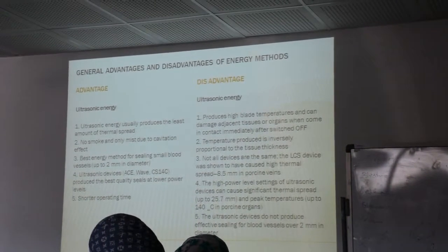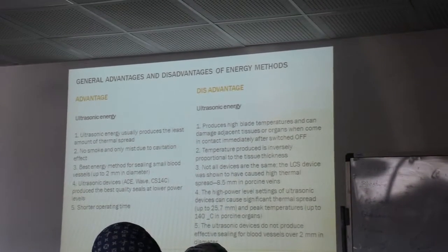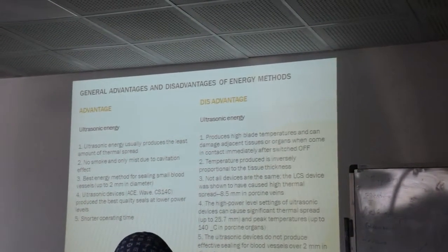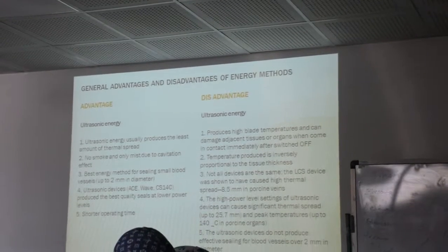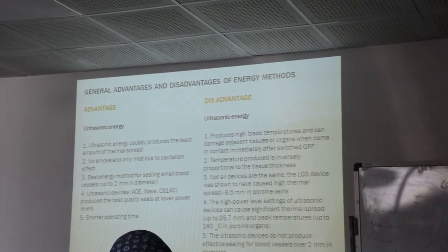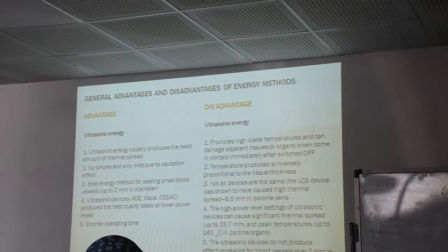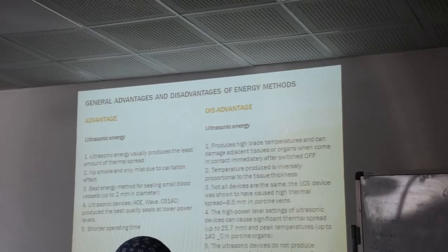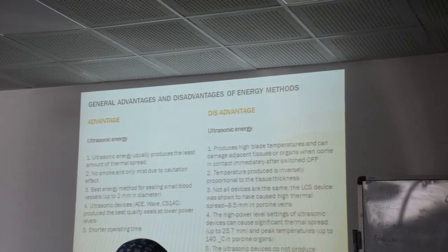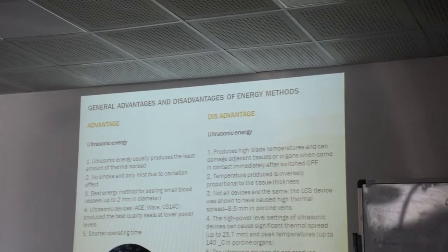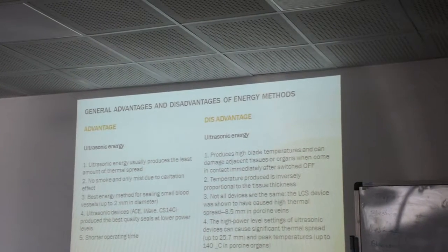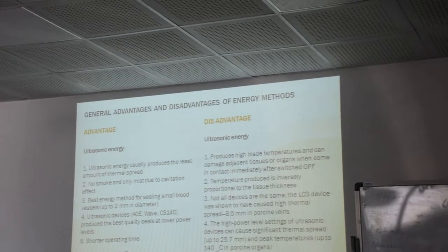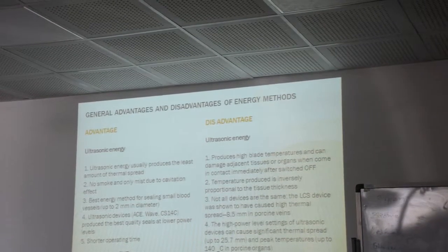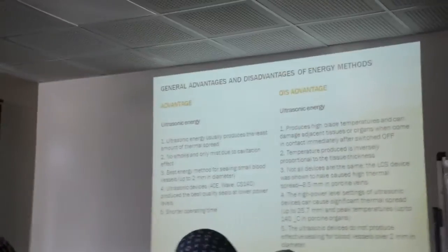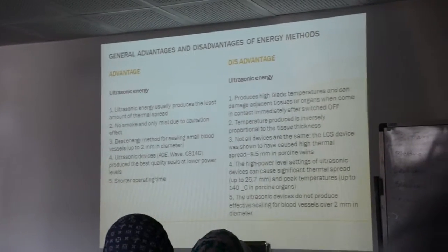The LCS device was shown to have caused high thermal spread, 8.5 millimeters in porcine veins. The high power level setting of an ultrasonic device can cause significant thermal spread, up to 25.7 millimeters, and peak temperature up to 140 centigrade in porcine organs.